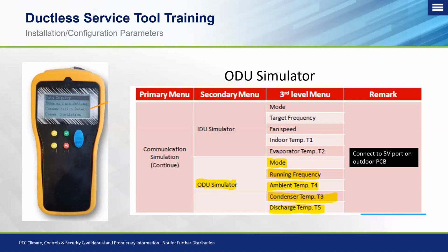And just like we did on the indoor unit side of things, remember that the temperature sensors are in degrees Celsius. We need to convert over to Fahrenheit. And of course, typically the rule of sensors is plus or minus 2 degrees for a sensor to be considered working or reading properly.